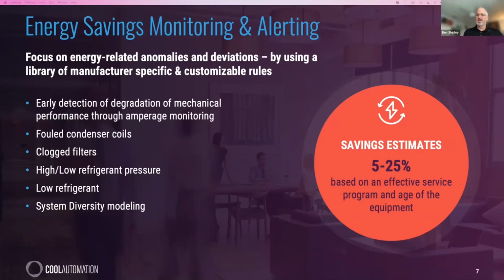With most VRF and HVAC systems, you have the ability to measure the current draw coming in from the mechanical unit. By measuring that current draw, you can establish a baseline for the usage of that unit or system, and then set a triggered event that indicates when it deviates from that respective amperage.